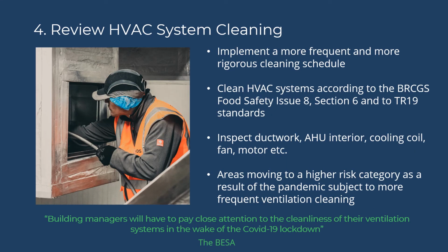Industry experts are predicting a greater focus on ventilation hygiene in the wake of COVID-19. The Building Engineering Services Association, BESA, has said that a more frequent and rigorous cleaning schedule is recommended. They say that it is more important than ever for systems operating on full fresh air that the ductwork is properly clean, and point out that if a facility needs to move to a higher risk category as a result of changes brought about by the pandemic, it will be subject to more frequent ventilation cleaning.